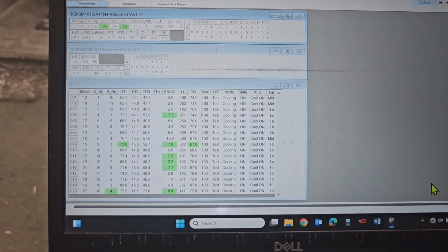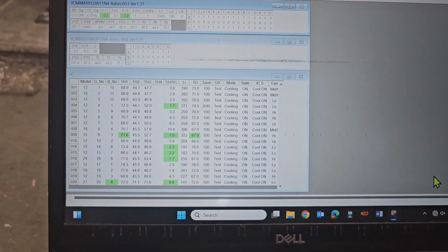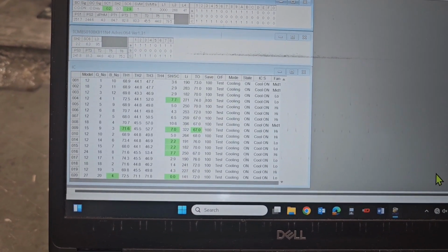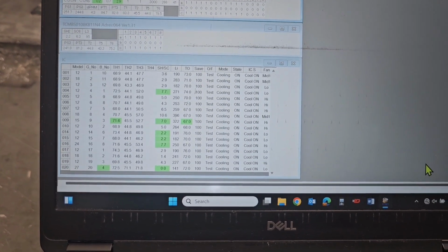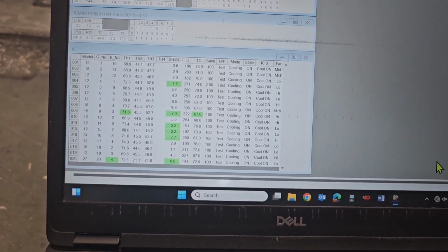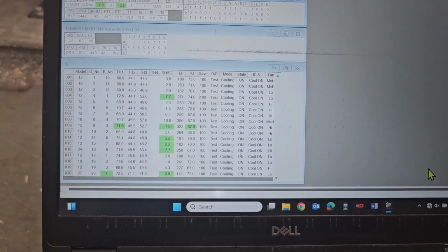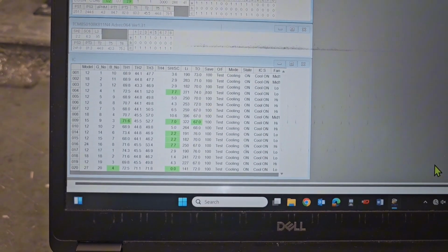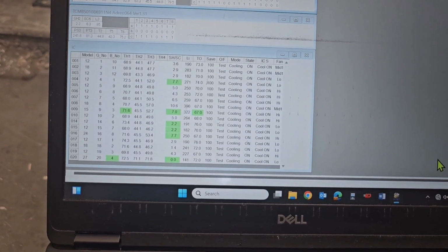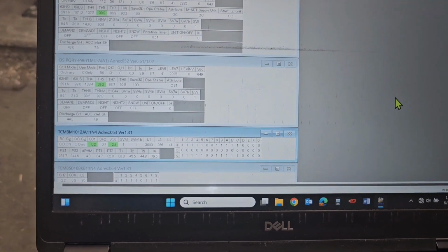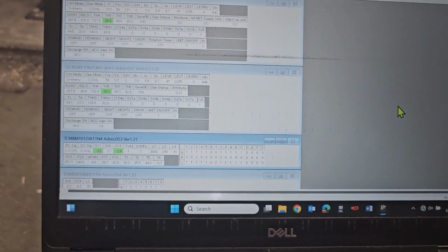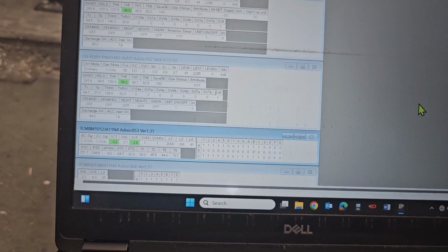Nothing worse than getting a log and it's in cooling for 10 minutes and then I start to see something and then it goes into heating for 15 minutes and then it's off and then it goes into cooling mode for another 15 minutes because people just won't leave it alone. Put it into cooling, put it into heating, and just leave it alone and watch it. That's the only way you're going to get reliable data. The system has to run for a long time to get balanced out and to start giving you valuable information.